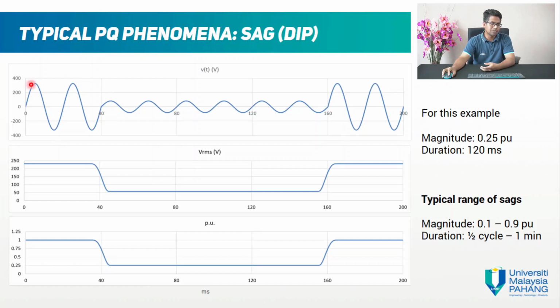230 volt, so the peak goes around 325 volt, and it's oscillating at 50 hertz, okay, 20 milliseconds for one period. It looks like this. It should be like this all day, all the time. But sometimes it will go down to become smaller amplitude like this. Okay, so how do we calculate this voltage sag?